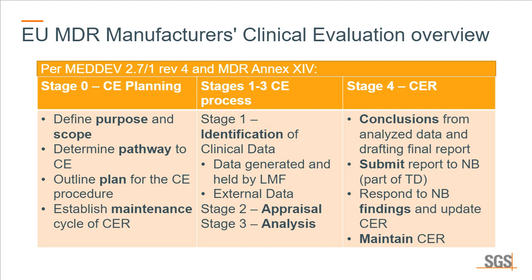Whereas when you are searching to show evidence that your device does not pose unacceptable risk, your search terms should usually be cast wider and be more broadly worded, because devices that might be more different than your device, but share common functionalities, may still be relevant for the safety claims. So let me give you an example.